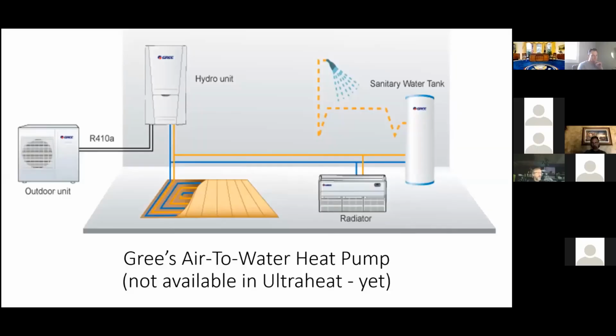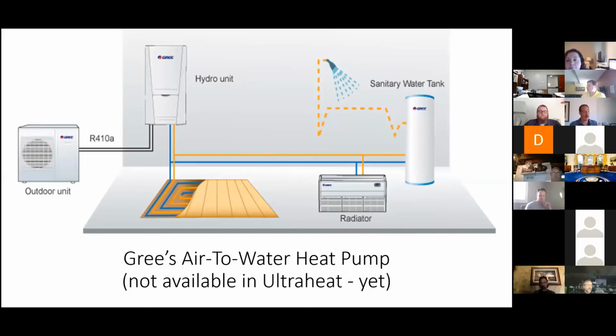This is not an UltraHeat product yet, but if you're considering eliminating gas from a facility and you don't want to use an electric hot water heater, we do have a heat pump slash hydro box slash hot water heater system. I don't know that this is going to take off like wildfire quite yet until they get the UltraHeat, but you can do an all-electric building and take advantage of the COP that heat pumps generate.